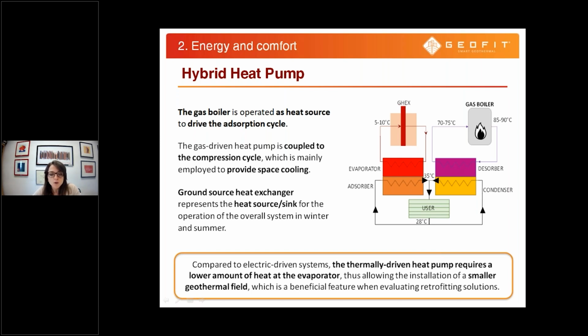Using this design, we were able to minimize the dimension of the geothermal field, which was important considering this was a historic building with a limited range of action in terms of stability of the system and drilling. This was done using the hybrid heat pump, because the thermally driven heat pump requires a lower amount of heat at the evaporator, which allows us to produce a smaller geothermal field.